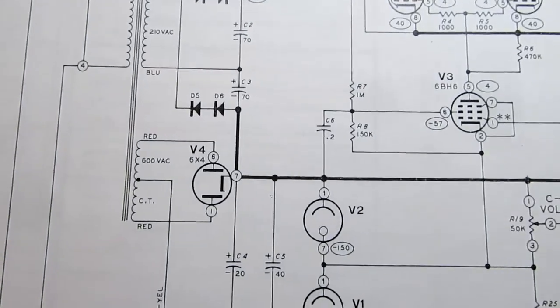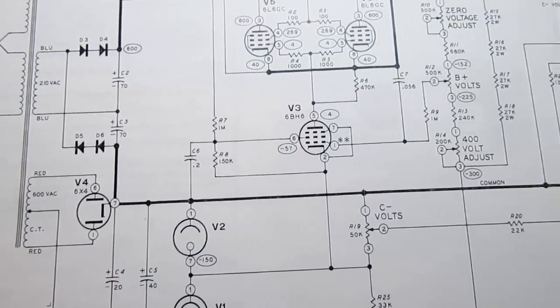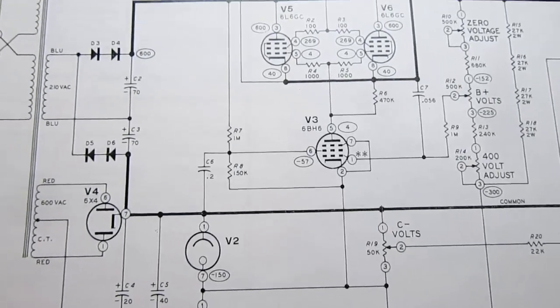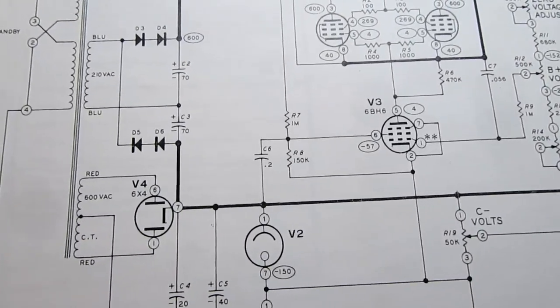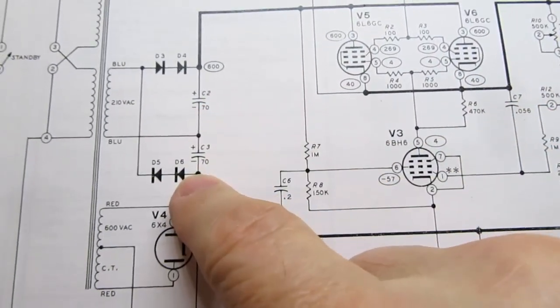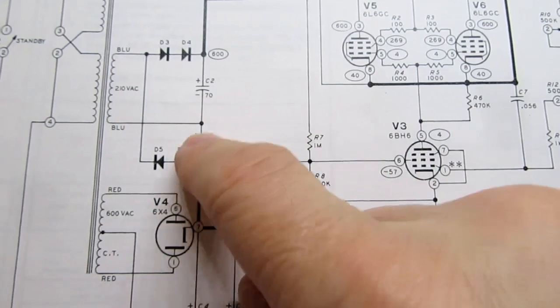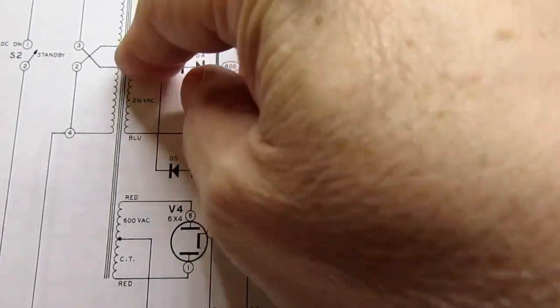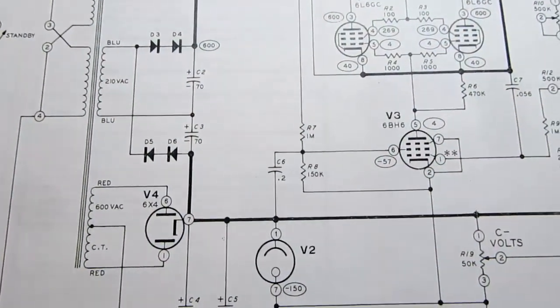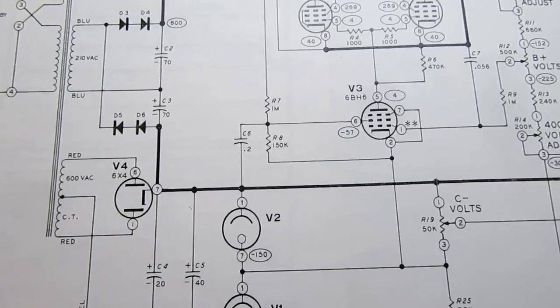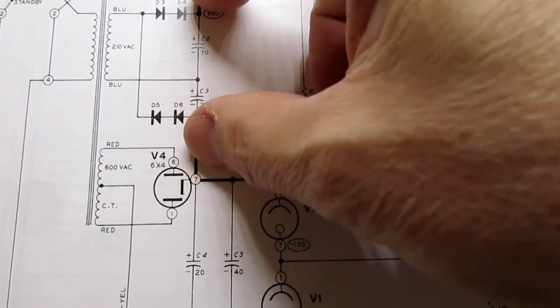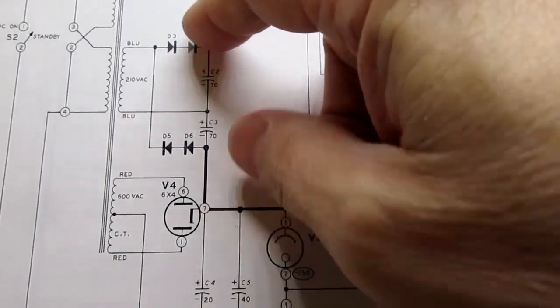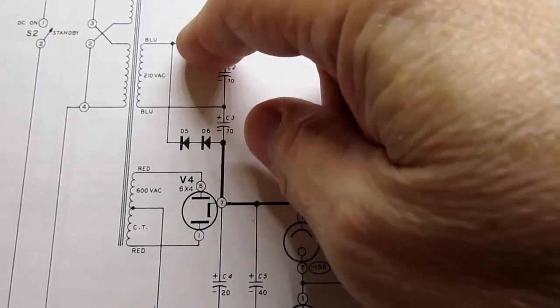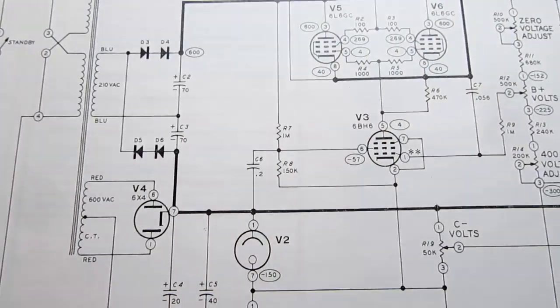And again, the current draw is pretty small on this. The circuit's only rated for 100 milliamps continuous maximum. So it's considered that these caps have enough capacity to maintain reasonable voltage during the half cycle when they're not being charged through the diodes. And anyway, the output can only go up to 400 volts, so we are developing 600 volts here, which is 200 volts more than the highest output voltage. So you can actually have quite a bit of sag on the caps during the half cycle when they're not being charged, and it's still adequate.